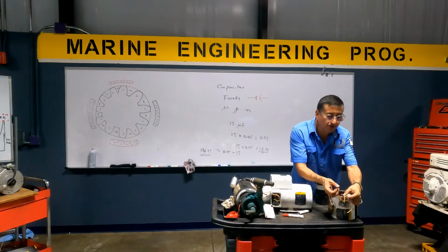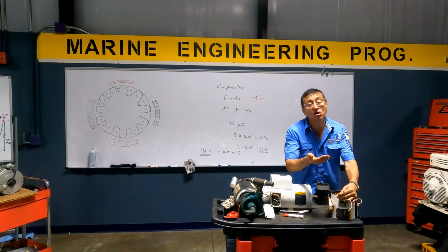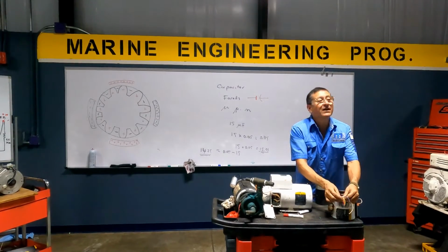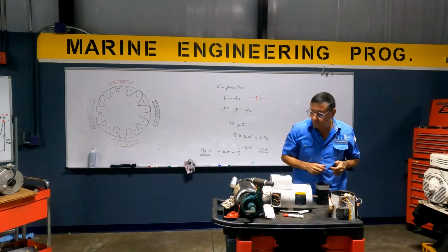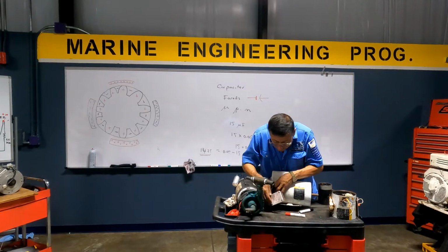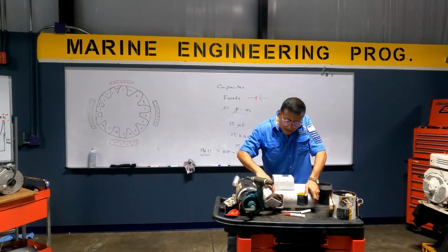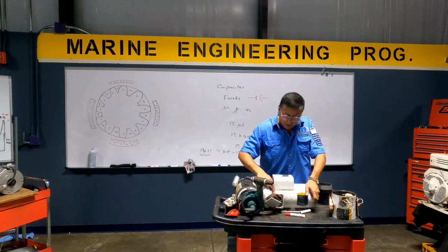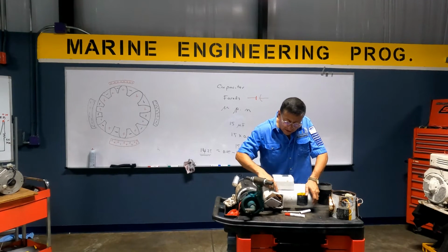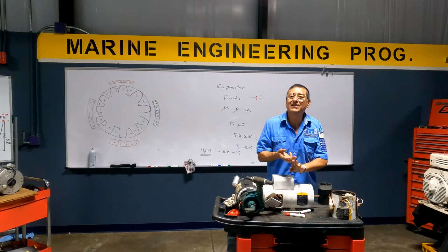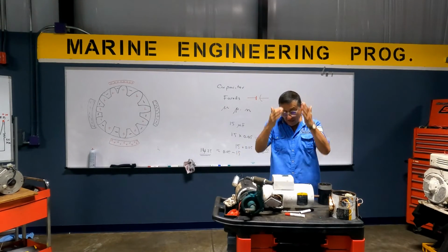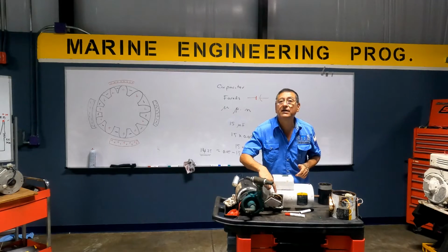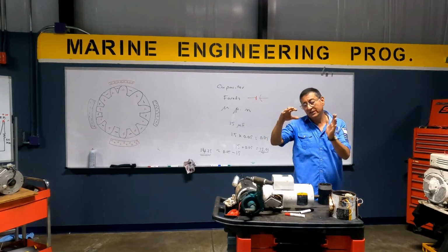And depending on the combination of those phases, I have low speed, high torque, or reverse rotation. When you play with the phases, you have different options. For that reason, you see on the plate of the motor here, if you put together 1 and 3, and the other one with the green with the yellow, you have low torque. In this configuration, you have high torque, in this one high speed, in this one low speed. Depending on how you connect it, you have this 3-phase motor for high torque, low torque, high speed, and low speed, and you have the configuration here on the plate. All the 3-phase motors have that option.